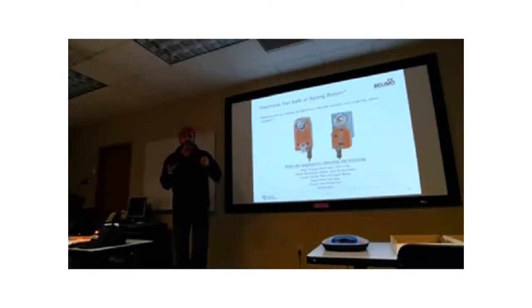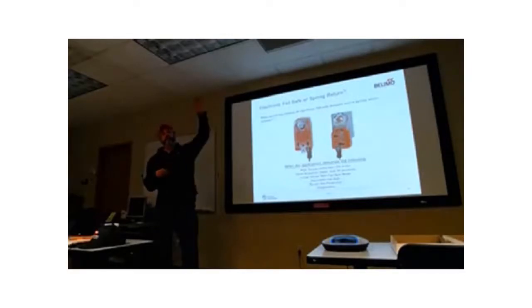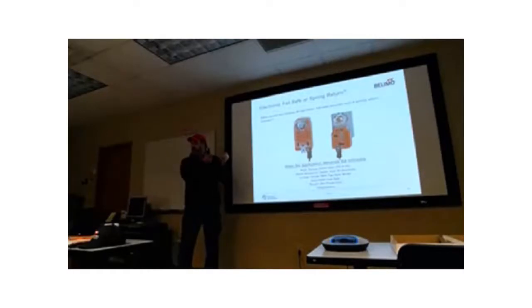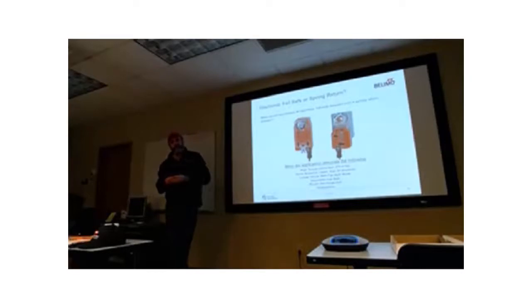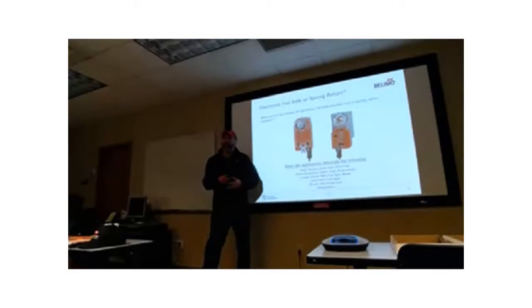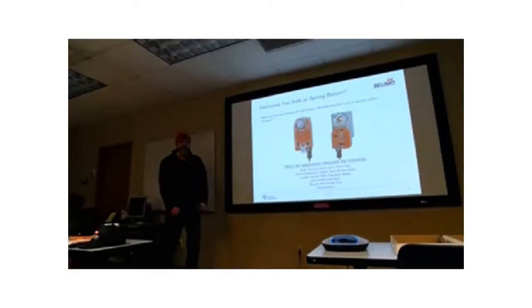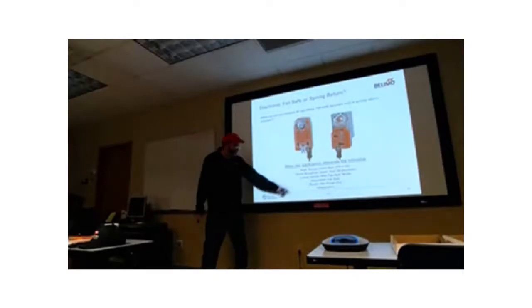I don't know if you guys know this application, but we did it down in Portland. We had a huge, well, a 40-story building with a penthouse - built-in penthouse, walls of dampers, probably 35 feet high. They all were pneumatic plunger actuators, the ones pinned at the end, just plungers connected to drive clips on the dampers. What we were able to do is put in these electronic failsafe linear actuators, and we just dropped them right in and pinned them at the end. Now, if we didn't have those linear actuators that were failsafe, it would have been a pain in the butt - we would have had competing crank arms and things like that. It wouldn't have been fun. So that's a good application there. The adjustable failsafe I talked about.